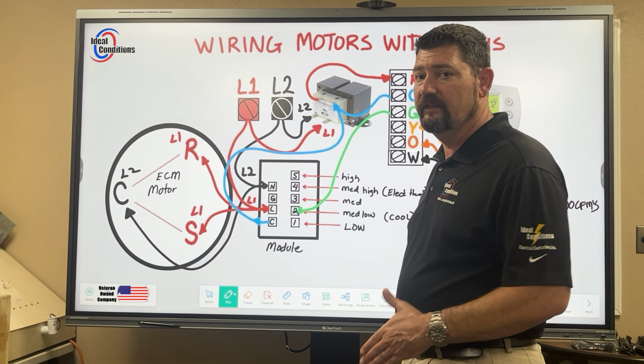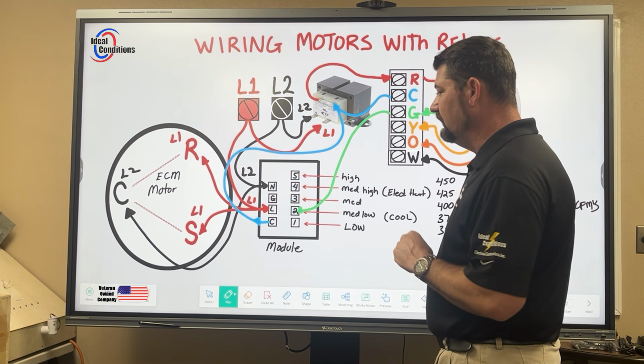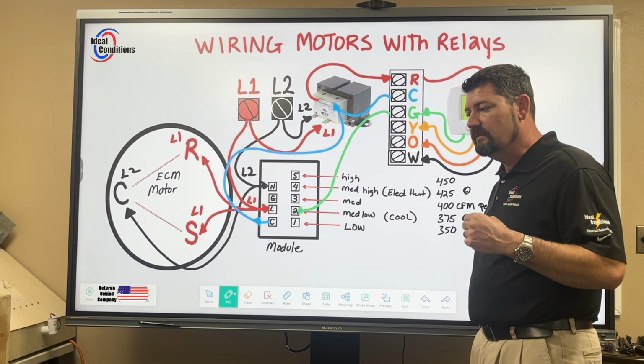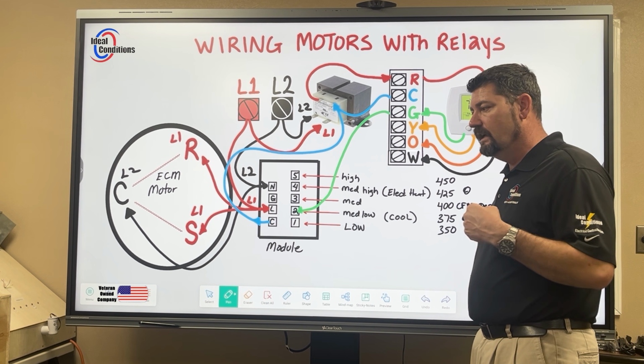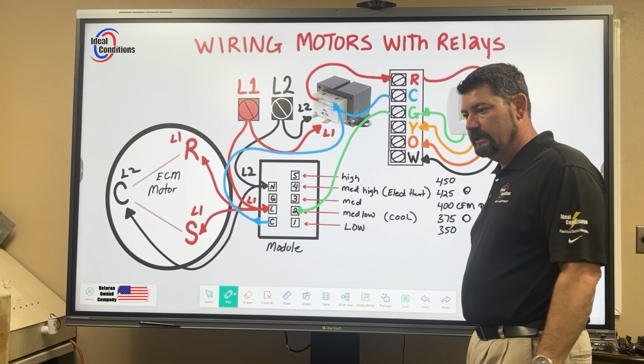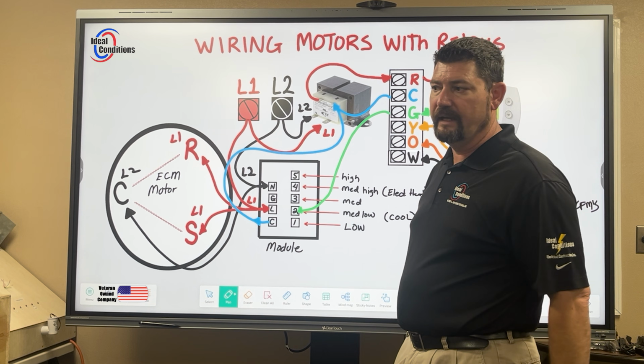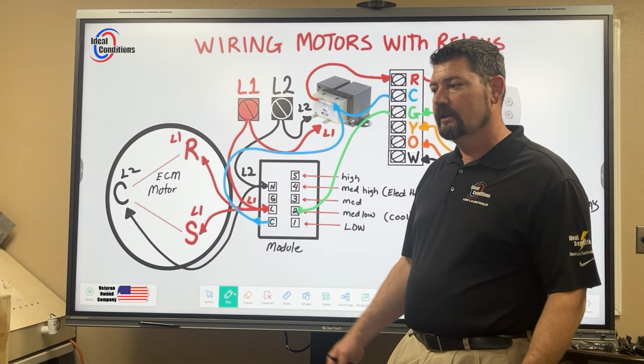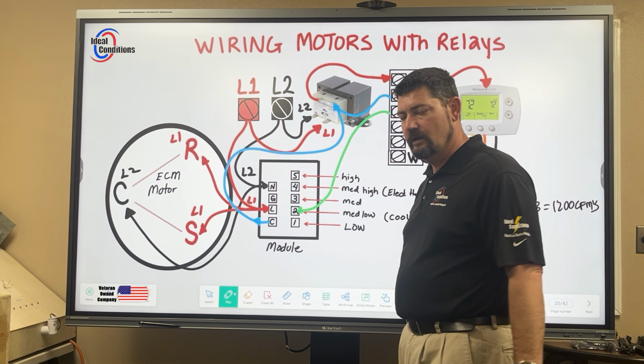Here you're going to have 90 seconds. Now, the problem with that 90 seconds that I see in our industry is the misdiagnostics that come out of it. Hey, my motor won't shut off. Okay, what do you think it is? Oh, the module's bad. Well, why do you say that? Because when I remove the call for G, it won't shut off.